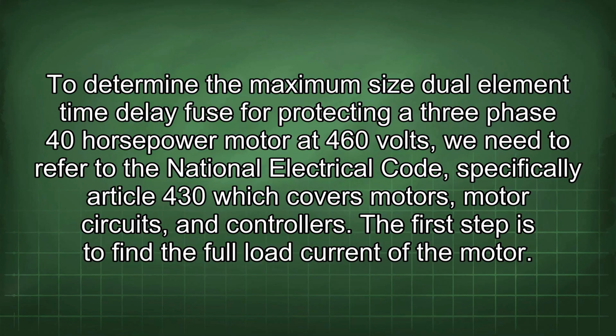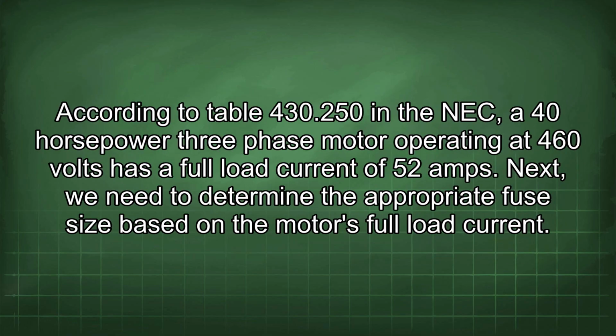To determine the maximum size dual element time delay fuse for protecting a 3-phase 40 horsepower motor at 460 volts, we need to refer to the National Electrical Code, specifically Article 430, which covers motors, motor circuits, and controllers. The first step is to find the full load current of the motor. According to Table 430.250 in the NEC, a 40 horsepower 3-phase motor operating at 460 volts has a full load current of 52 amps. Next, we need to determine the appropriate fuse size based on the motor's full load current.